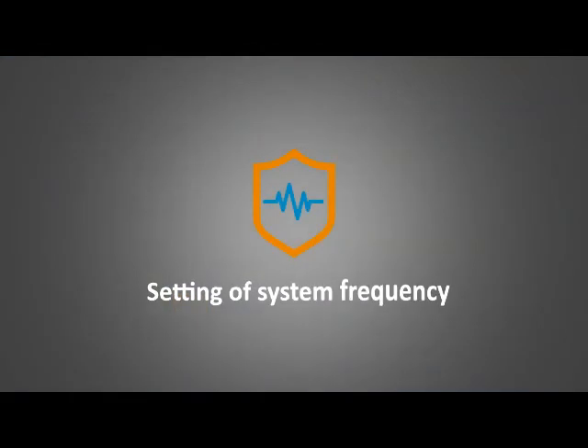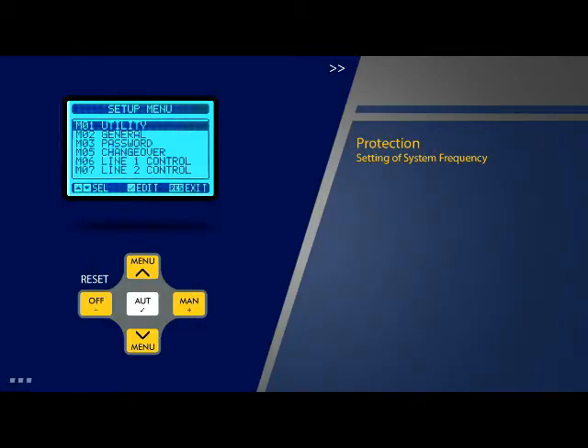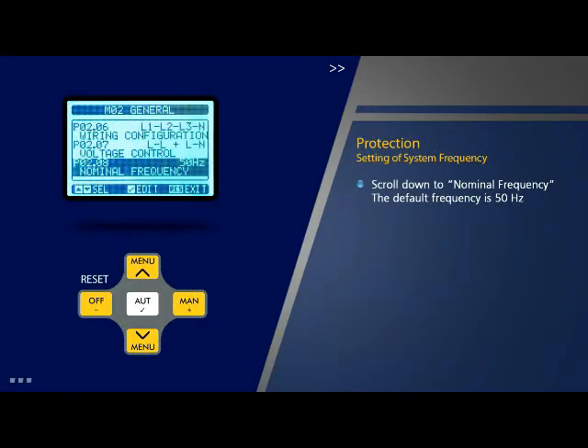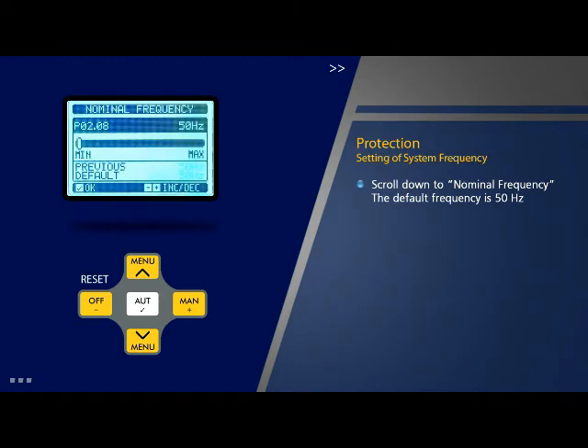Setting up system frequency: Scroll down to parameter 8 which is 'Nominal Frequency' on the general page and press OK. The default frequency is 50 Hz. Scroll to change the value to 60 Hz and press OK. Now 60 Hz is the new default frequency.